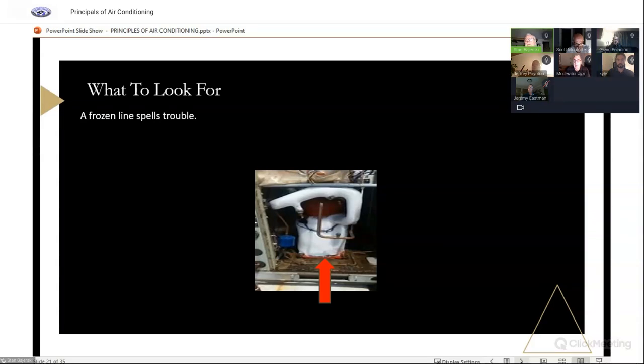Hey, Stan, with a heat pump, I know this is a little off topic, because that could be running year round. Does that mean you should get it cleaned twice a year? I don't think you're going to clean it in the winter. Okay. I mean, if you want to pay to have somebody come, you can clean your own. If you disconnect the power, take the top off, blow some air through from inside out. If it's really greasy, grimy, you use a degreaser, hose it down carefully so you don't bend the fins. Right. But how many homeowners do you know that are going to go out and clean their own condensing coil? They're not. No one. So once a year, probably even for a heat pump, we're going to touch base on a heat pump a little bit towards the end of the presentation. Okay. So if you see this, it's definitely a big problem.